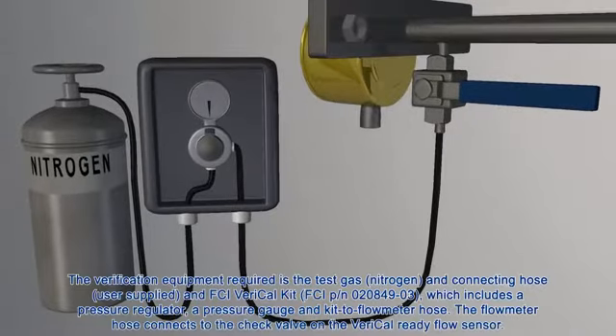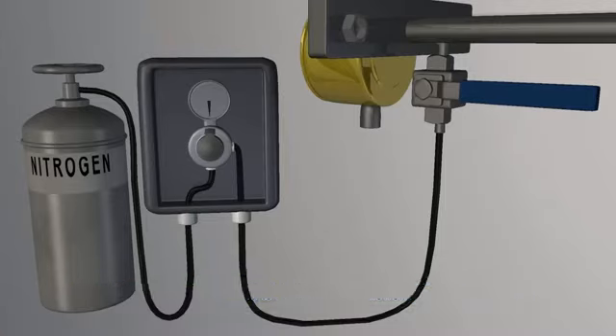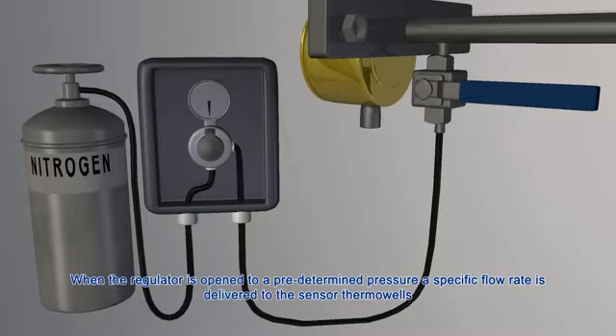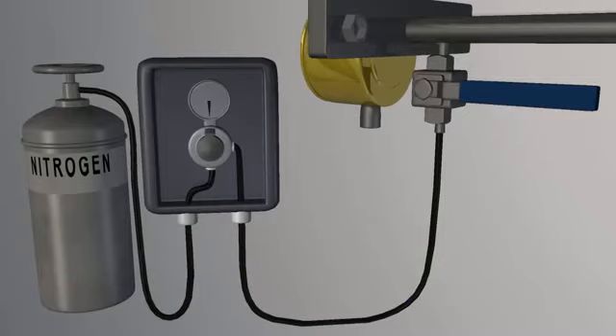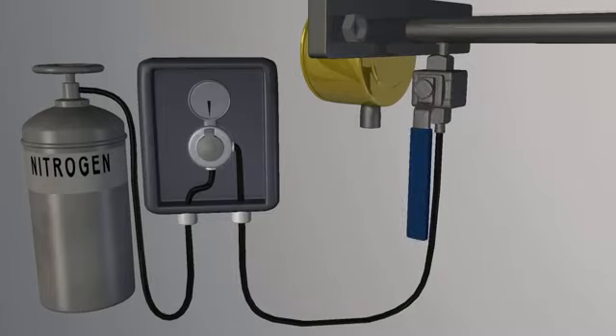The verification equipment required is the test gas, nitrogen, and the connecting hose, which is user supplied, and FCI's VeriCal kit. The kit includes a pressure regulator, a pressure gauge, and a hose connecting the meter to the VeriCal kit. When the regulator is open to a predetermined pressure, a specific flow rate is delivered to the sensor thermowells through a sonic nozzle.